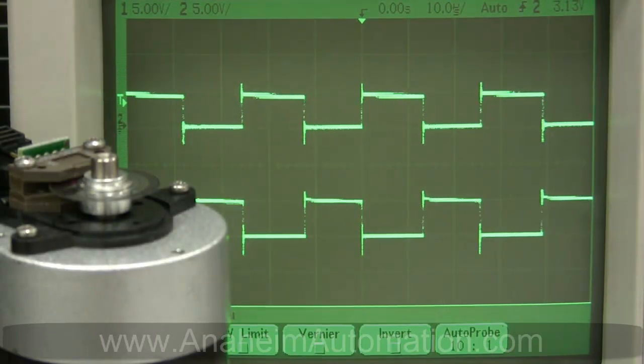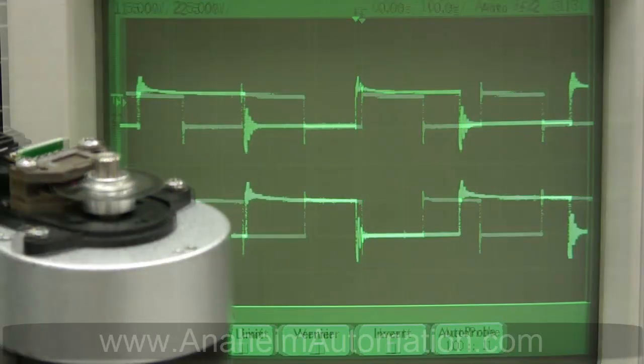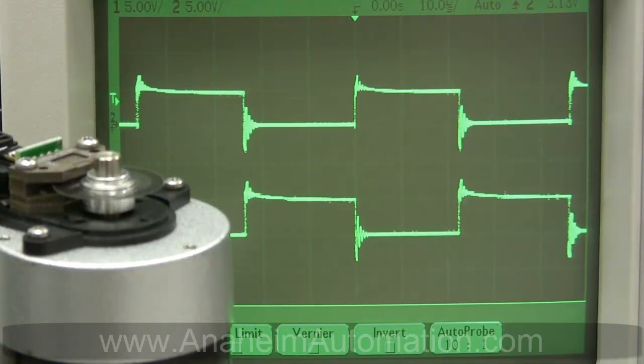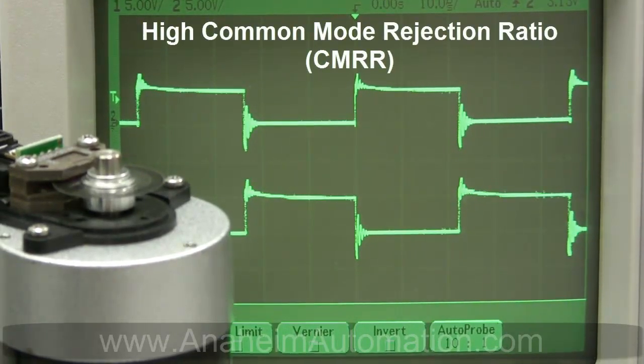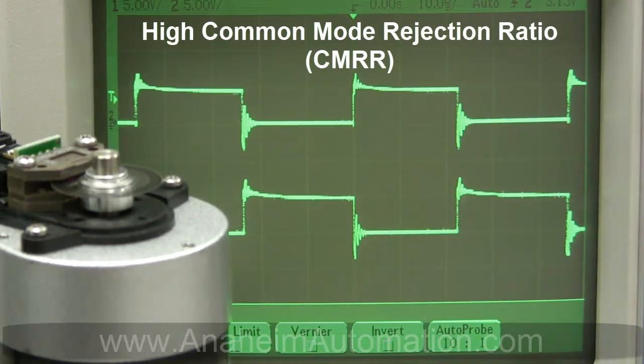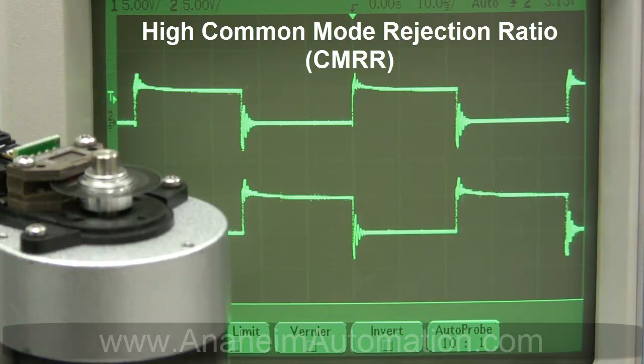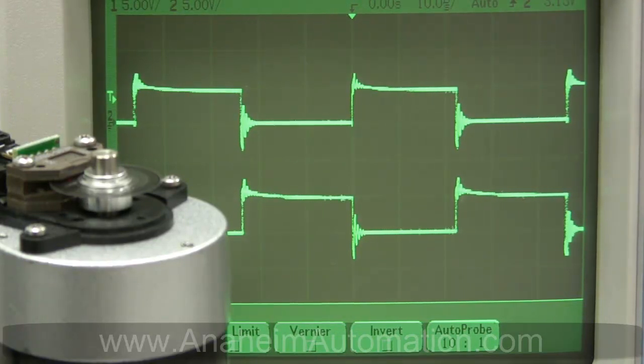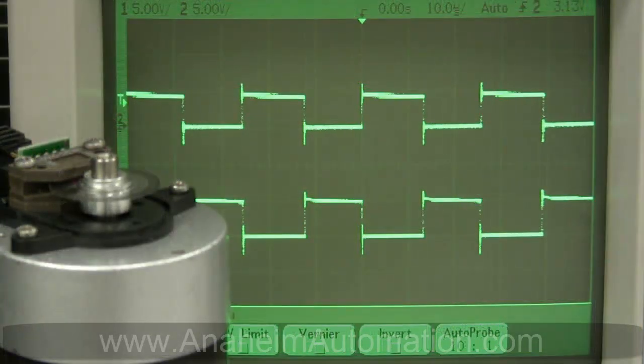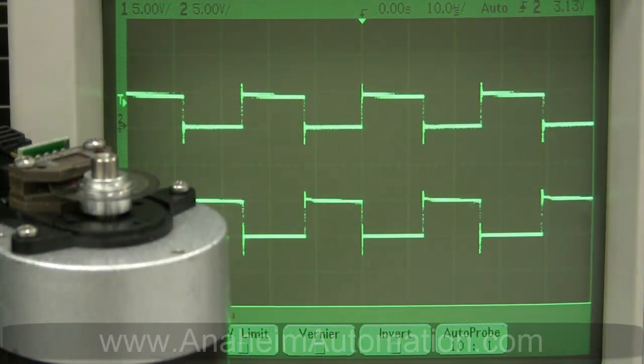As a result, any noise evident in both wires is cancelled. There will be some offset between the voltages, which is expressed as a common mode rejection ratio, also known as CMRR. This allows for differential encoders to be used with longer cable lengths, up to 4,000 feet.